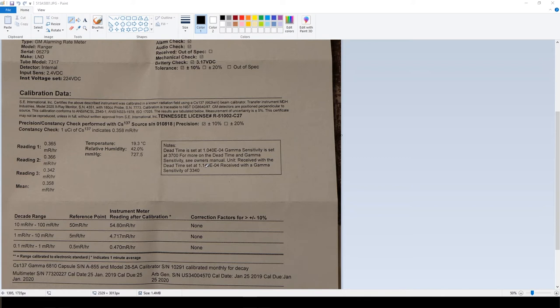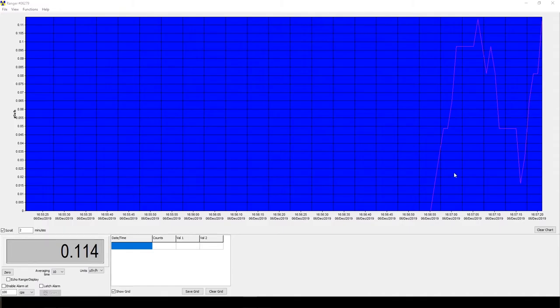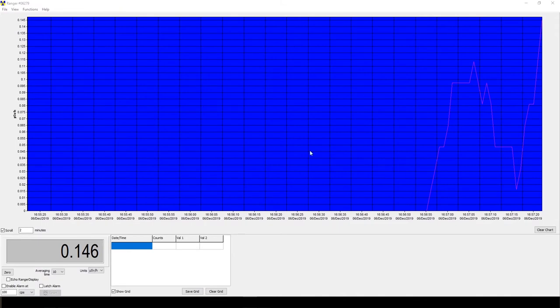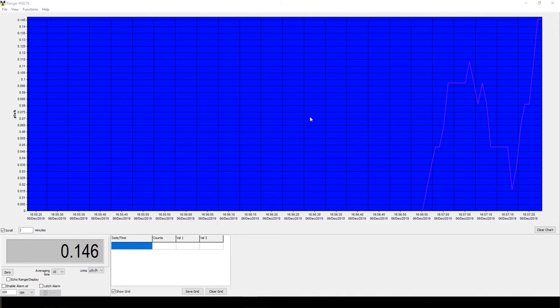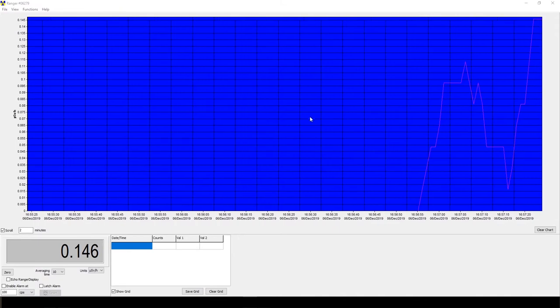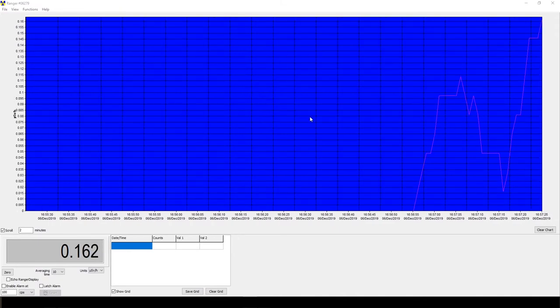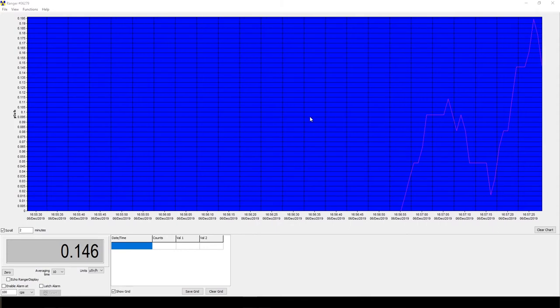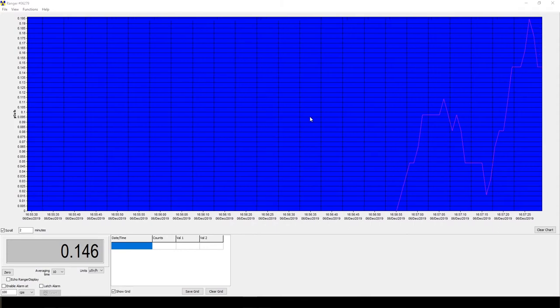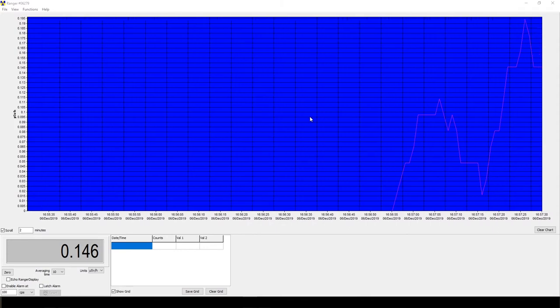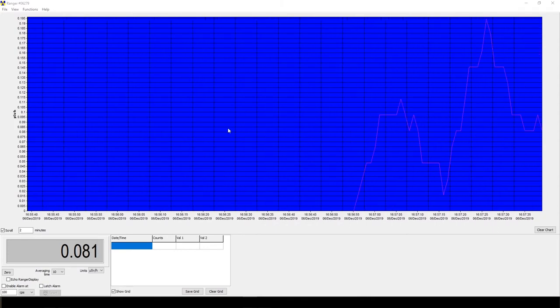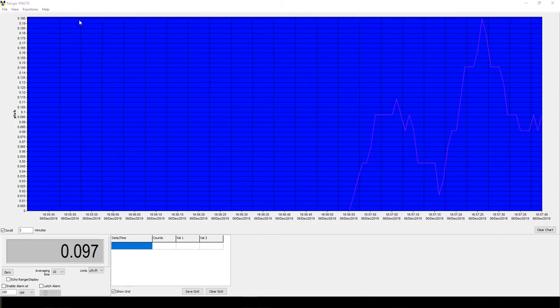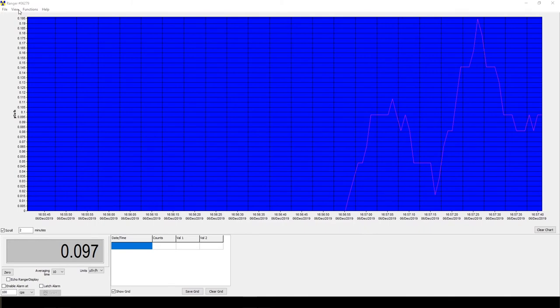Right here we got Observer USB pulled up right now, which is SE International's free software that you can download from their website. To see what they actually changed in the calibration, we got to go up here to View.